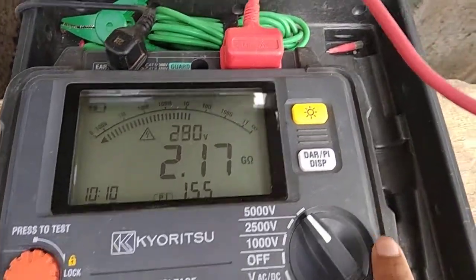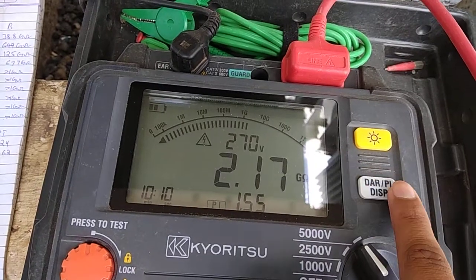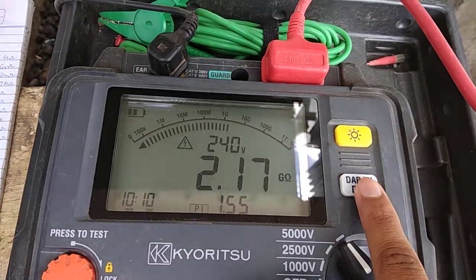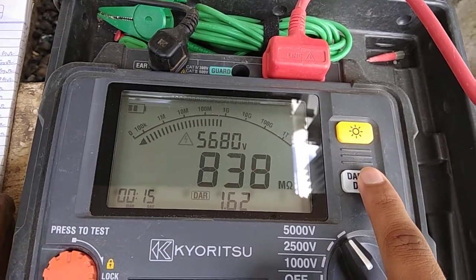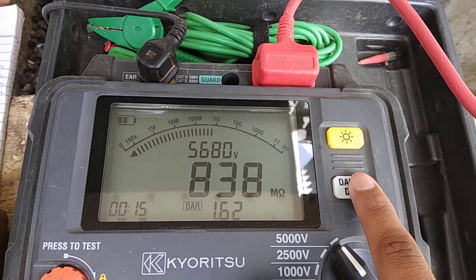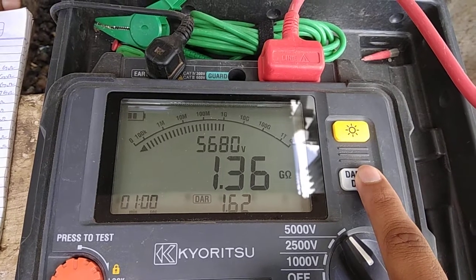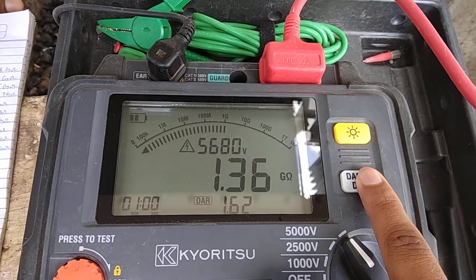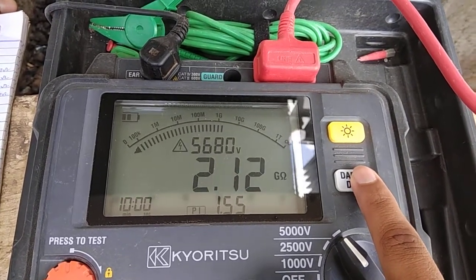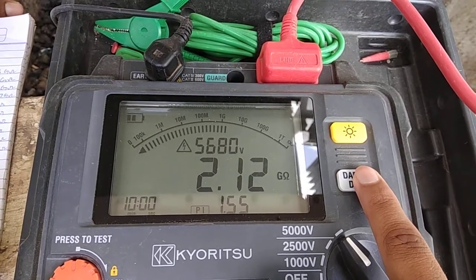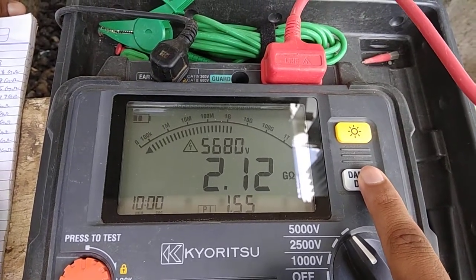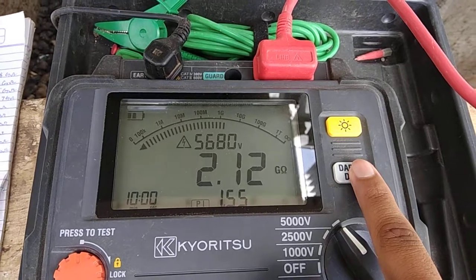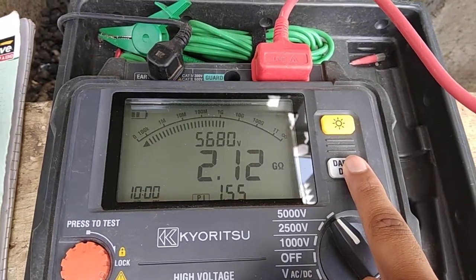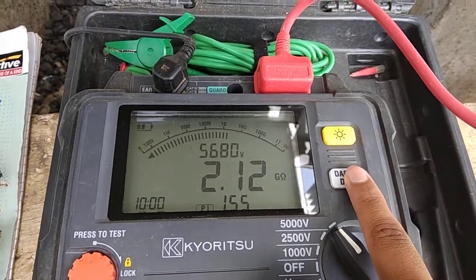So if I show you carefully, the PI value is 1.55. The value after 15 seconds goes to 830 mega ohm. After 1 minute, 1.36 giga ohm. The current reduced, that's why the resistance increases. And after 10 minutes, it's 2.12. The current also decreases. And the PI value is 1.55. And this is in the acceptable range. And the transformer PI test insulation is okay.